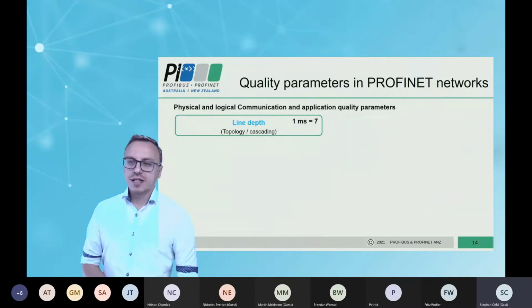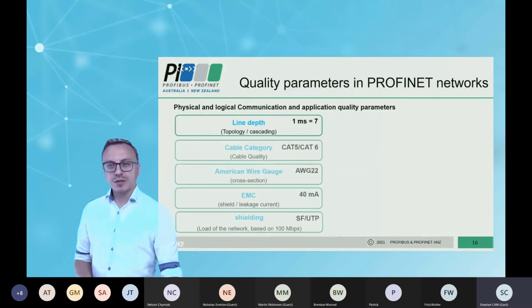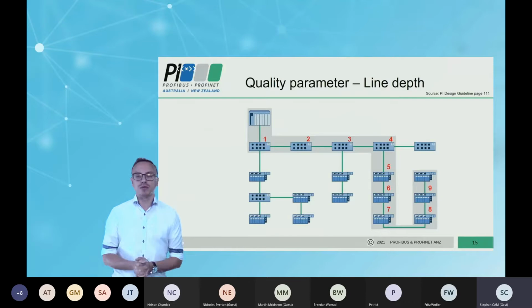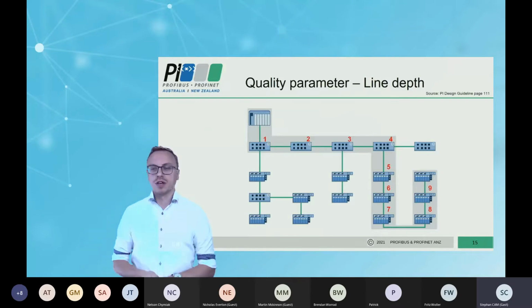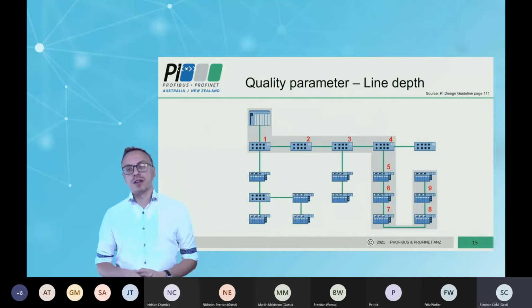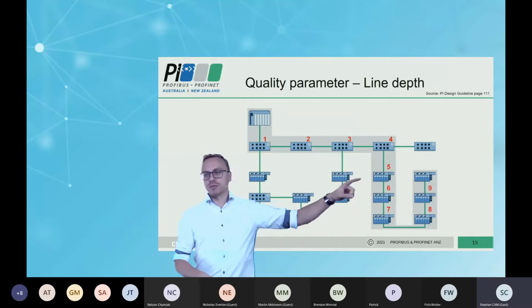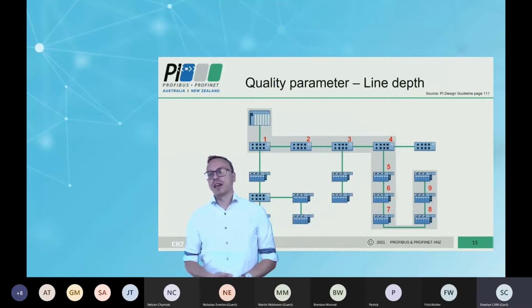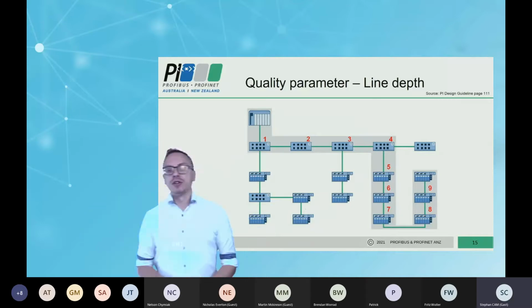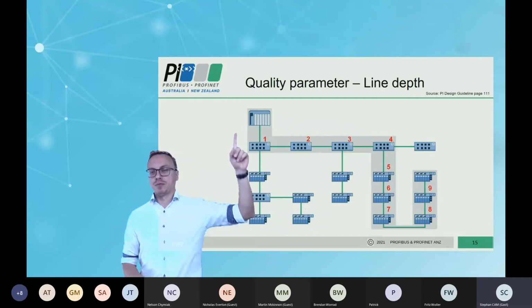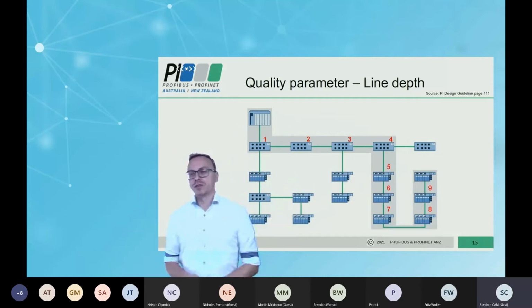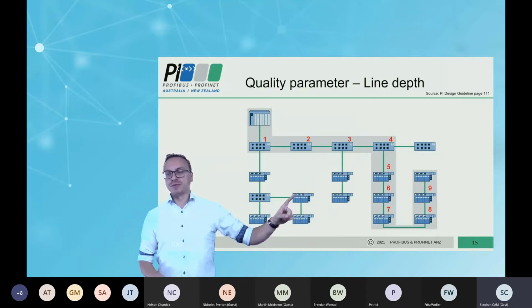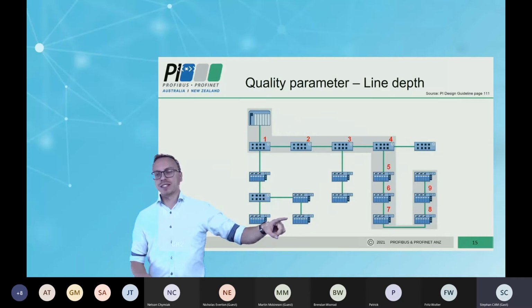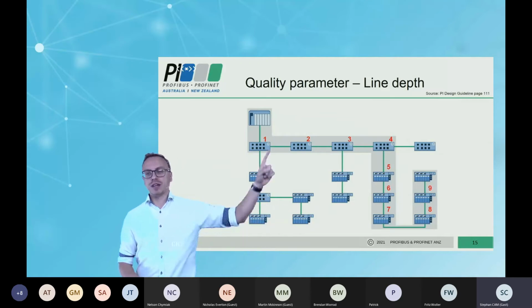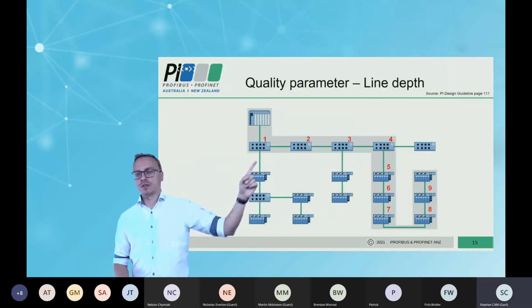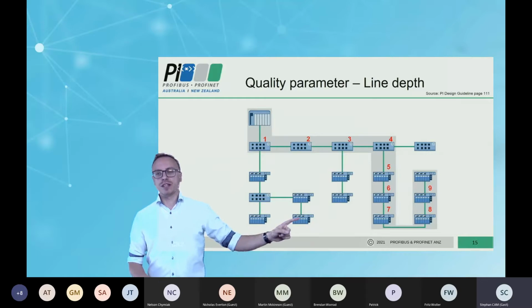Okay, let us start with line depth. Your line depth describes the cascading of your devices in your topology. But you have to know how to count it. For example, this device next to node number 5 has a line depth of 9. How do you count it? You count the devices between the PLC and the last node. For example, this device has a line depth of 4, because between this node and this node we have 4 devices: 1, 2, 3, 4. So this device has a line depth of 4.